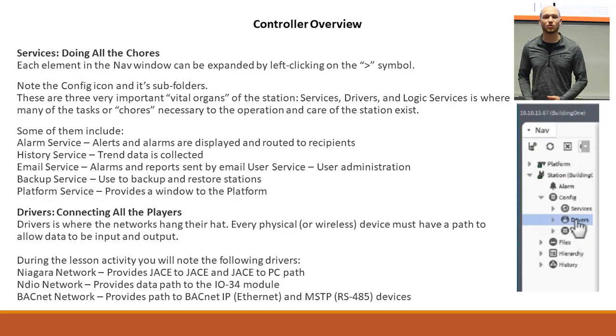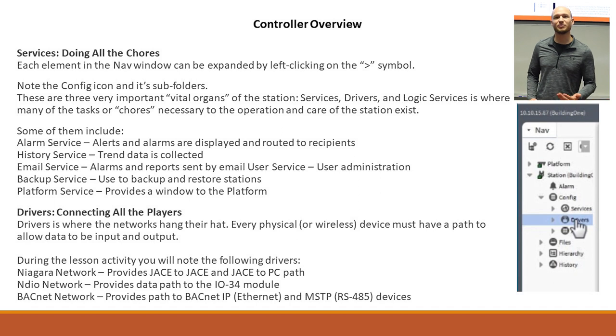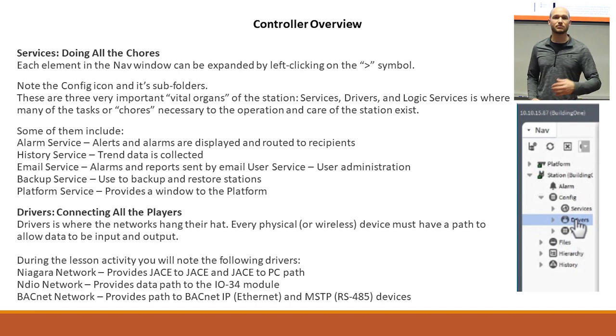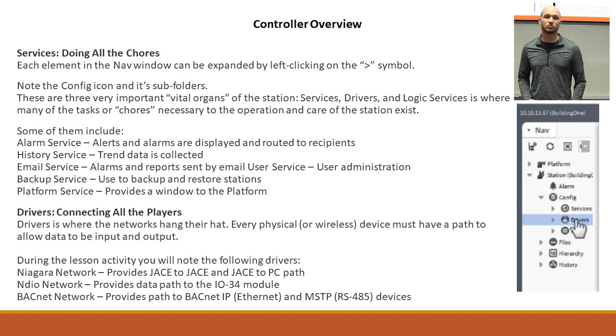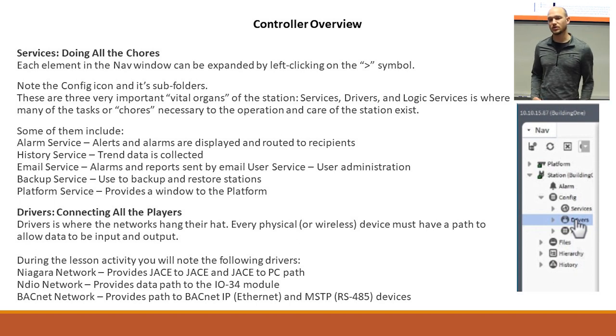Some of the things you can do inside the controller: services include alarms, history, emails, backup, and platform services. Then you get into drivers — BACnet is a very popular one, and if you're running LonWorks, you'd have a LonWorks driver. Different network protocols use different drivers. Typically you'll see the Niagara Network, NDIO Network, and the BACnet network as three good examples.